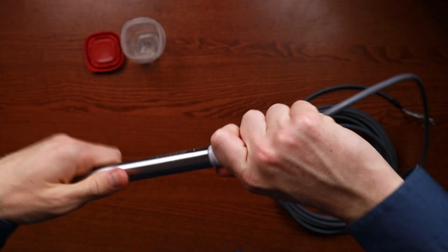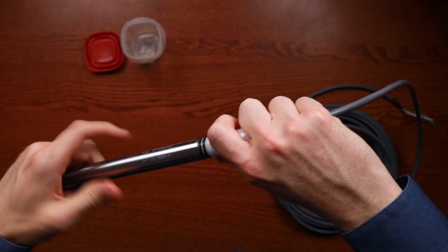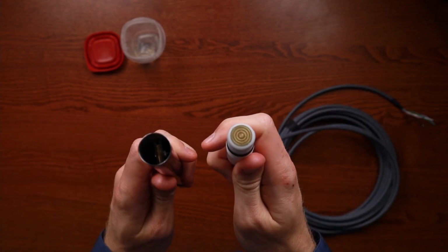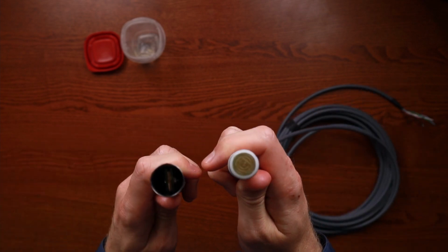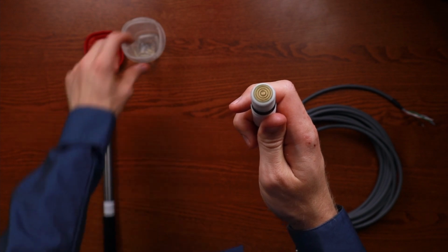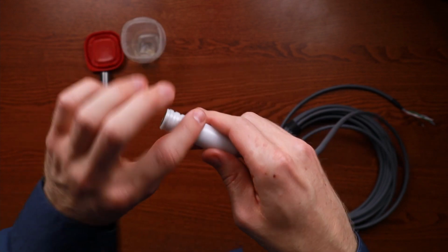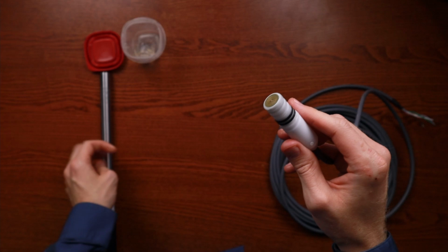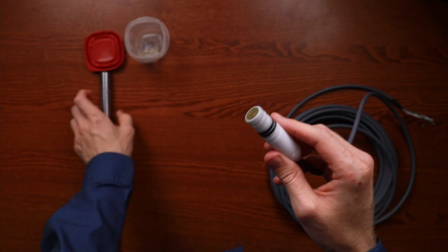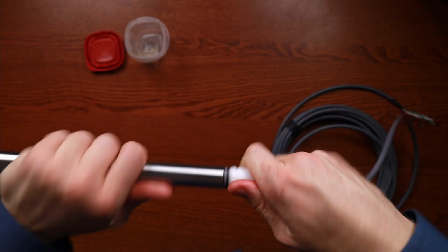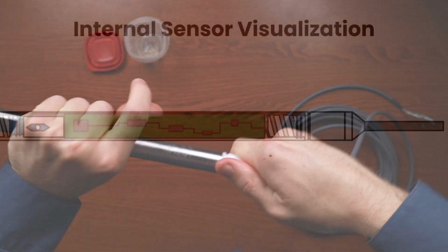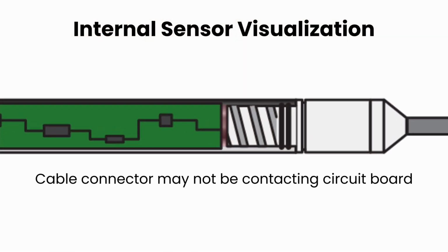Unscrew the connector and check for any debris that may be preventing contact on the end. Also, check that the circuit board connectors are not oxidized or damaged by looking inside the housing. Now is also a good time to grease the O-rings. Once done, screw the connector back in and see if a current is being output by the temperature wires. If there is still no output, then the circuit board is likely not contacting the cable connector.